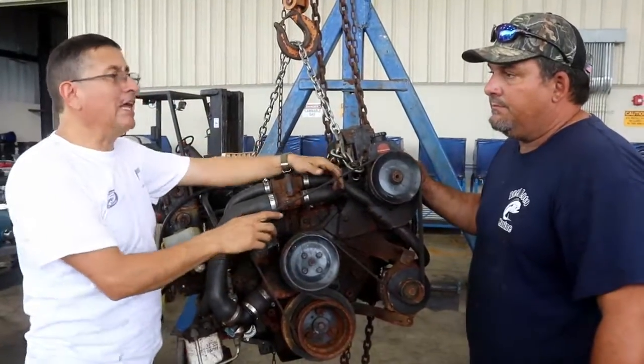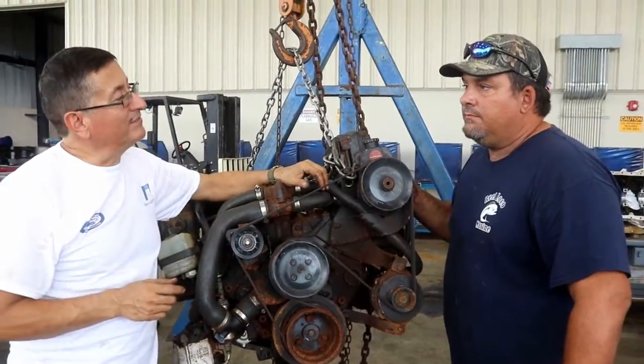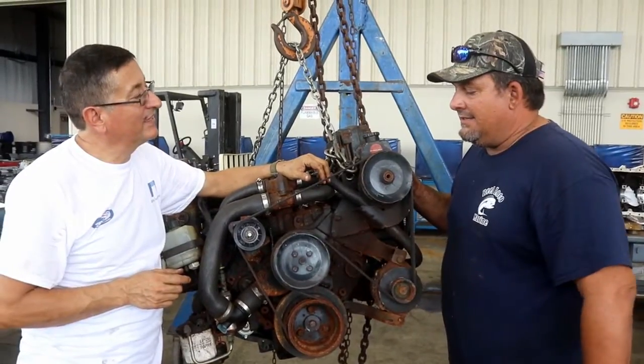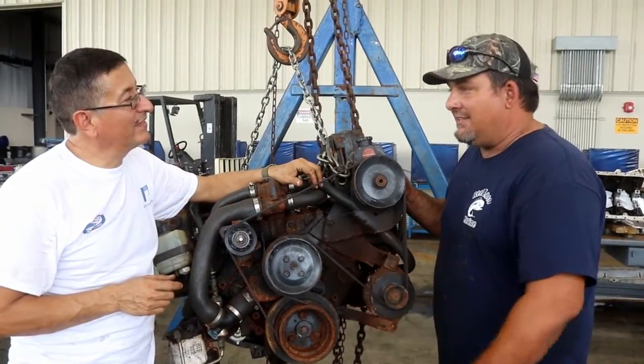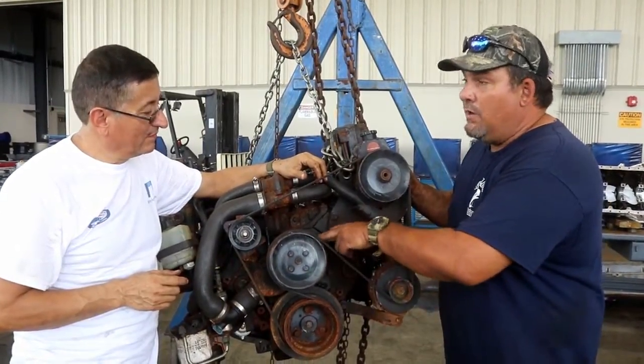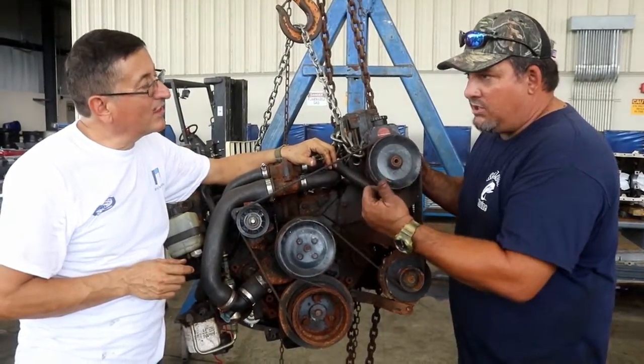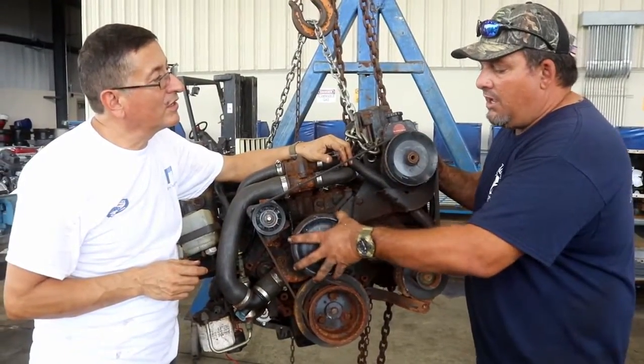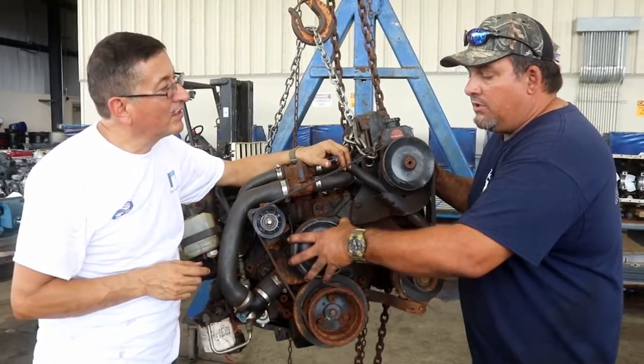That pump was designed to work with coolant. This one is designed to work with salt water, but it doesn't last as long. You have the same weep hole just in case there's leakage, if you have a bad shaft or a bad seal. When you take the belts off, make sure there's no play on them.